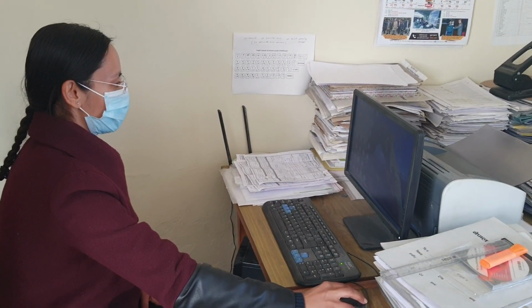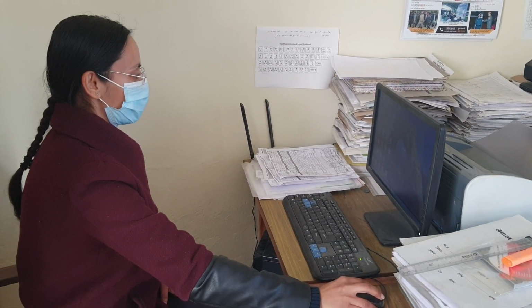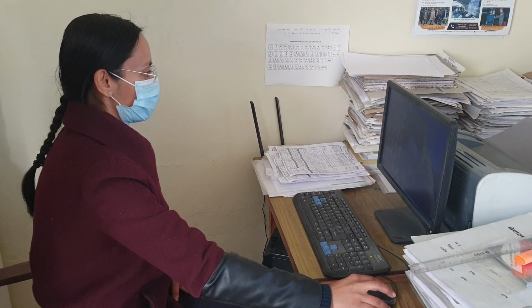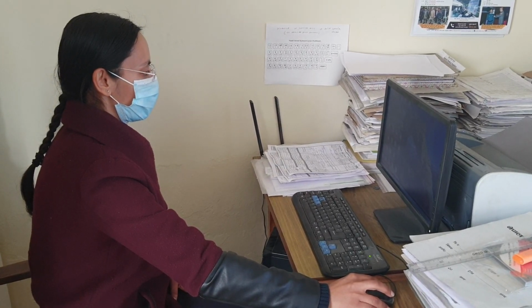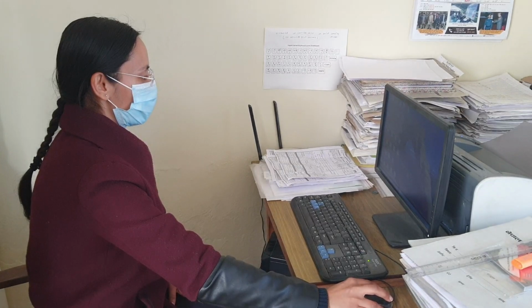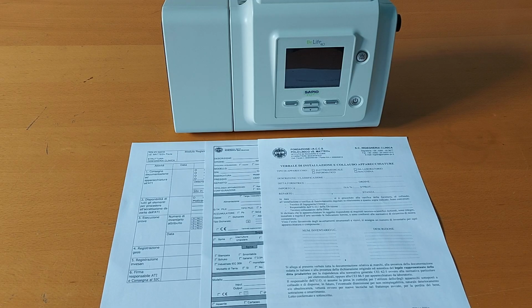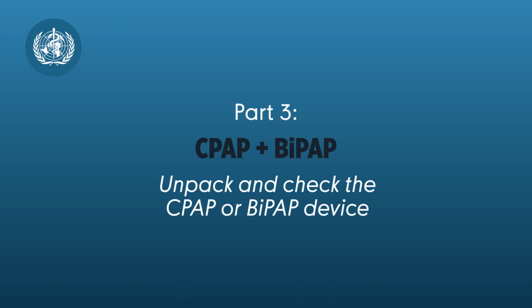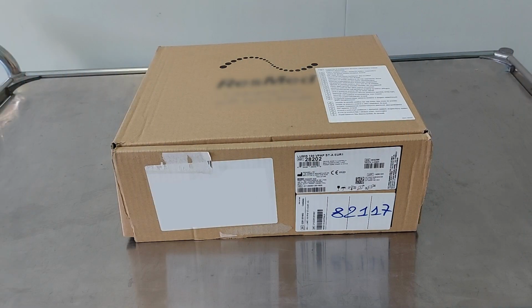Make sure you document the acceptance testing results in the database system you use at your healthcare facility to record device information, dates, schedules, and other data. If you don't use a database system, document the testing results on a checklist or paper record and file it in the equipment record. We will go over the setting up of CPAP in this video, and the same method applies to BiPAP. Now you are ready to unpack the CPAP or BiPAP and any other boxes that came along with it.